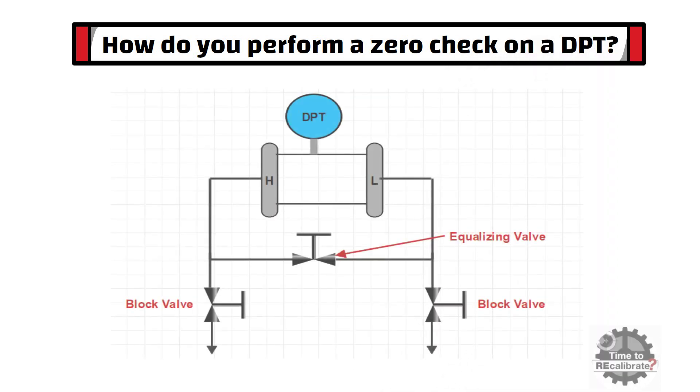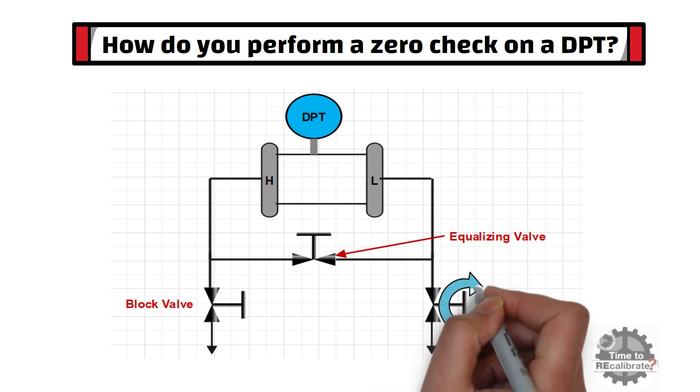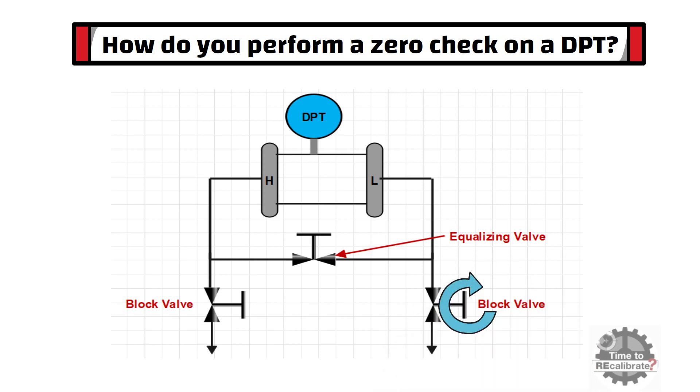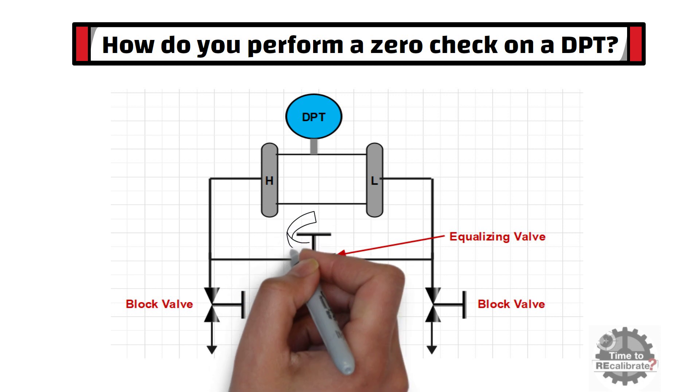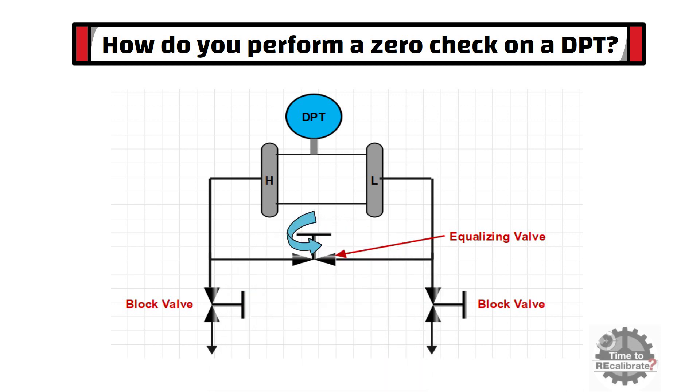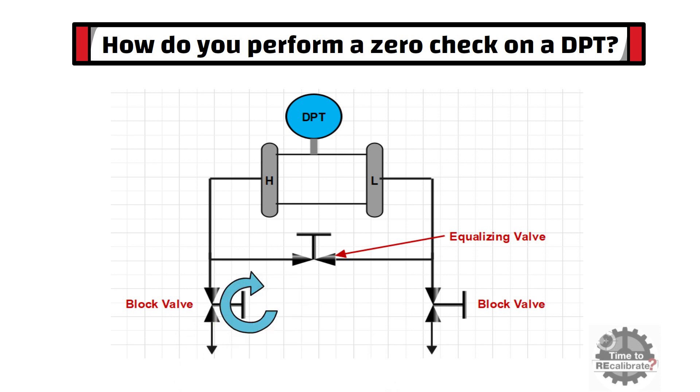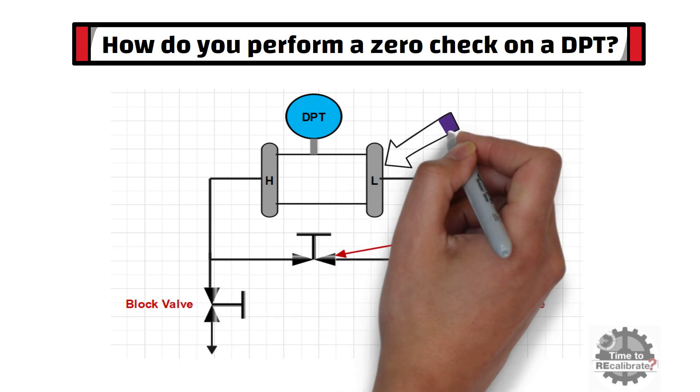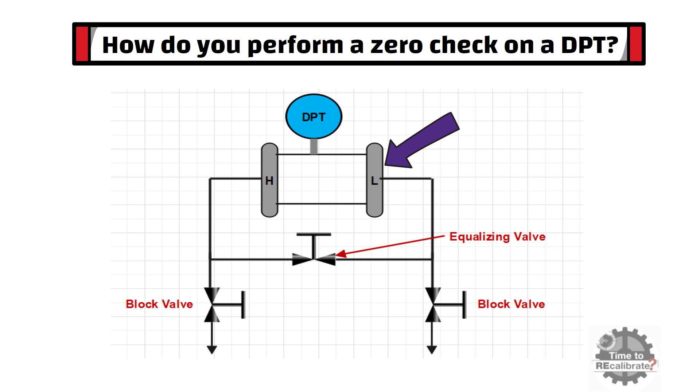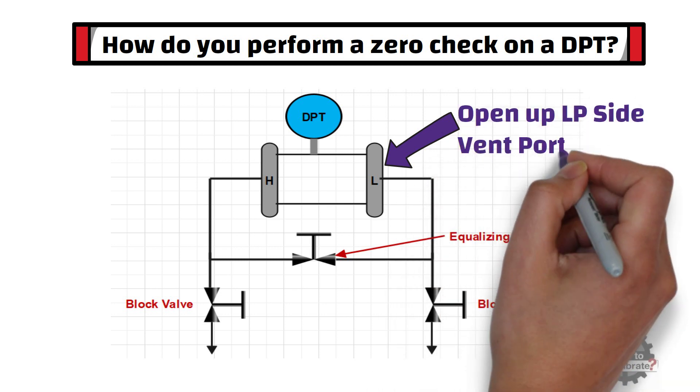To perform zero check of DP flow transmitter, a technician needs to close the low pressure block valve. Then he needs to open the equalizing valve. And finally, he needs to close high pressure side block valve. After performing final steps, he needs to open low pressure side's vent port.